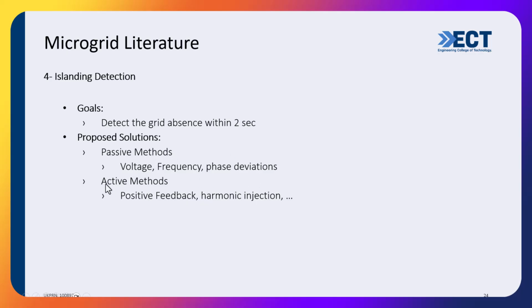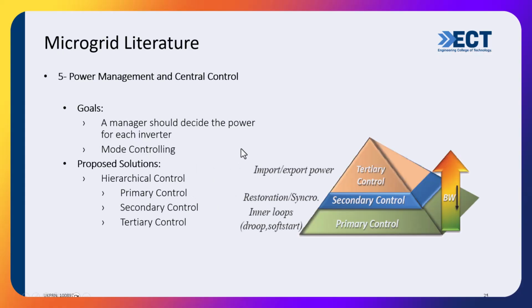They call it passive. Or there are active methods, where they, for example, inject some harmonics to test whether the grid is there or not. But maybe the most common active one is frequency deviation. In frequency deviation, you push the frequency a little bit outside the limit. If it comes back, that means the grid is there. If it doesn't come back, that means the grid is absent and we switch off.